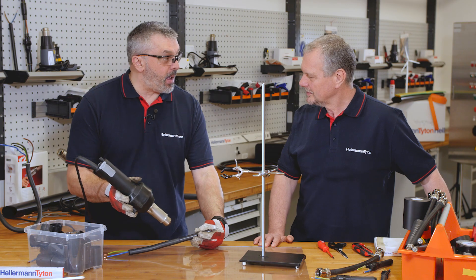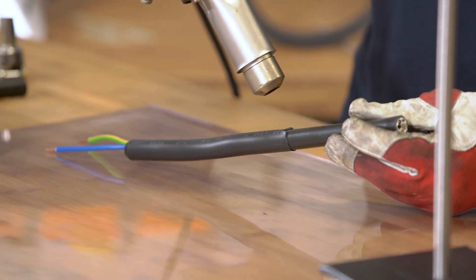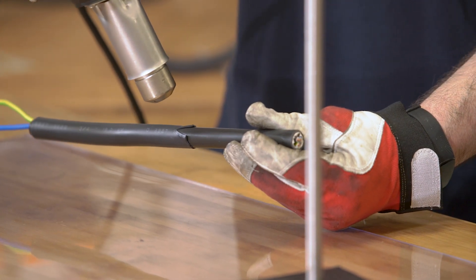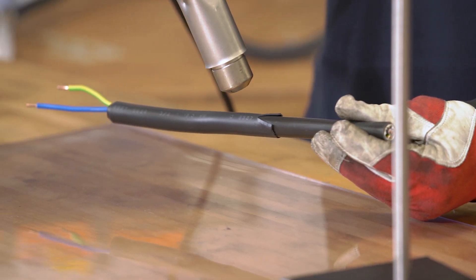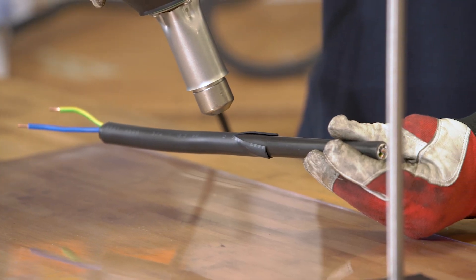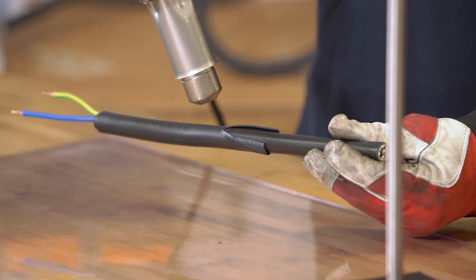In our last session we talked about memory. Well, this tubing has a memory as well, so it's still trying to recover, and what happens is it just splits. That one little nick will cause this — the tube can split all the way up if there's heat there.